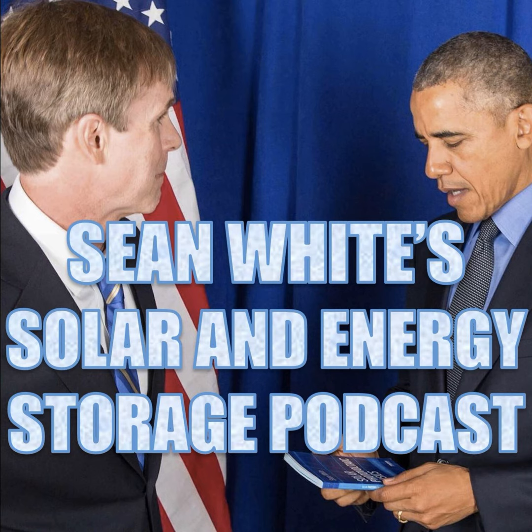Pretty much what we're saying here is if you have a building with different power sources and somebody's going to turn off everything, either we're going to have to go to 705.10 or 712.10. So there's going to either be a plaque or directory if these power source disconnects are in different places. But if they're all in the same place, so multiple power sources shall be permitted to be identified as a group, then you don't need a plaque. So pretty much what we're saying, this goes throughout a lot of the renewable energy stuff because we're going to have different energy sources. If all the energy sources are in one place, then when somebody wants to turn it off, they're there, they turn them all off in that one place.